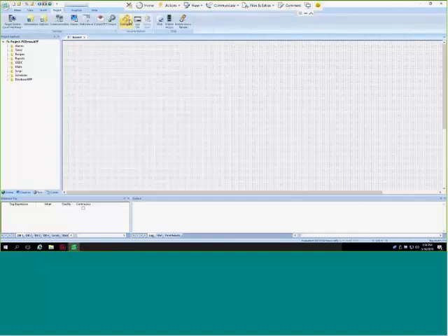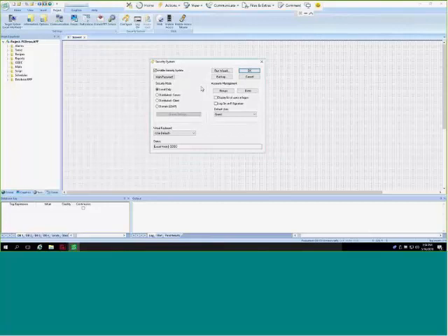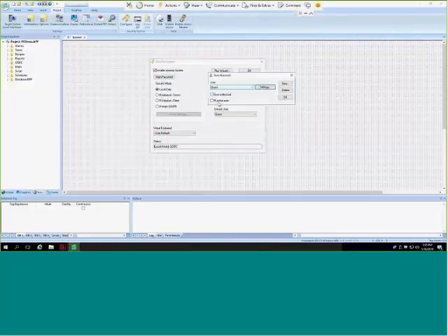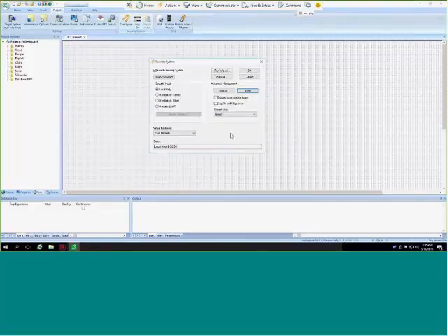Another thing worth mentioning is if you are using security, you need to make sure that the group that you are using has this particular feature turned on called Enable Remote Security System and Remote Debugging Tools. If that's not turned on, then you won't be able to connect. I also recommend, I'm not doing it for this demo, but you might want to create an individual user just for Win911, just for more transparency as to what's going on in the system. For this, I'm just going to use the guest account. So I wanted to talk about that before we actually connect.